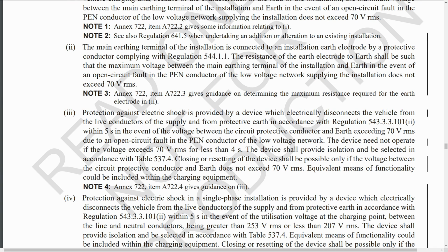Now, point number 2, this again is the same, although there has been some rearrangement of the wording. So the main earthing terminal of the installation is connected to an installation earth electrode by a protective conductor, and the resistance of this to earth shall be such that the maximum voltage between the main earthing terminal and earth in the event of a fault on the PEN conductor does not exceed 70 volts. So this is where you're putting an earth rod in, or more likely a huge earth mat under the ground, connecting it to the installation earth as well as the incoming PEN conductor.